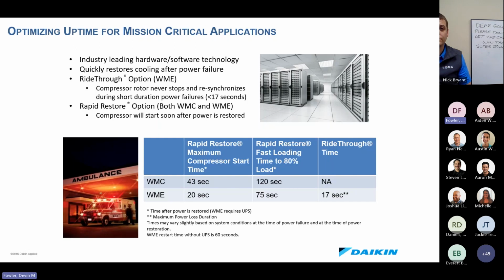With our magnetic bearing chillers, we're able to offer maximum uptime for what we would consider mission critical applications, such as hospitals or data centers. We do have industry leading uptimes, fast loading times, and we are the only chiller manufacturer in the industry that can offer what we call a ride through time. On our WME chillers, we can ride through a 17-second power outage. Most backup generators are spec'd to come on within 15 seconds. So if your site does have backup generators, you're never actually going to lose that chiller. Our compressor is going to stay operational throughout that entire 17 seconds. As soon as power is restored, it's going to ramp its speed right back to where it was before power was lost and continue on like nothing happened.